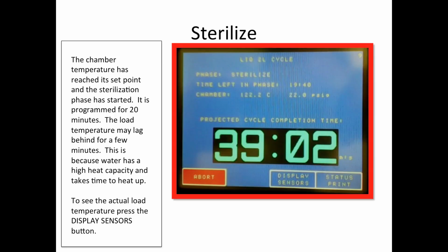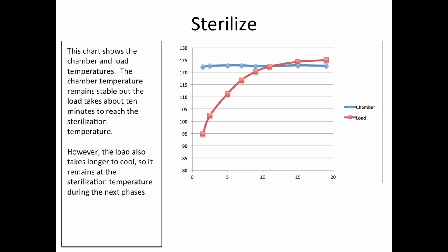Now the load temperature may lag behind the chamber temperature for a few minutes. This is because water has a very high heat capacity and it takes time to warm up. So to see the actual load temperature, you're going to press the display sensors button.